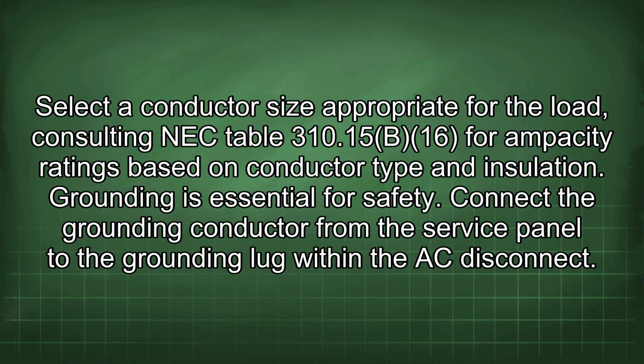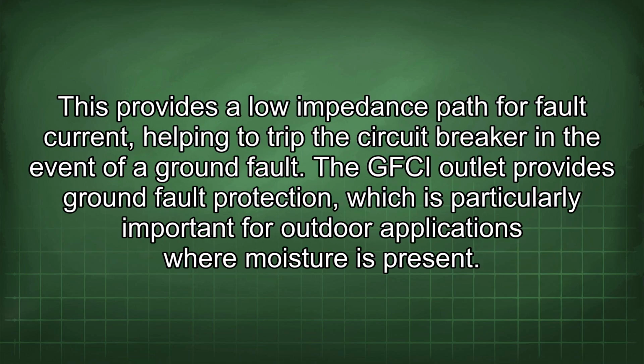Grounding is essential for safety. Connect the grounding conductor from the service panel to the grounding lug within the AC disconnect. This provides a low impedance path for fault current, helping to trip the circuit breaker in the event of a ground fault. The GFCI outlet provides ground fault protection, which is particularly important for outdoor applications where moisture is present.